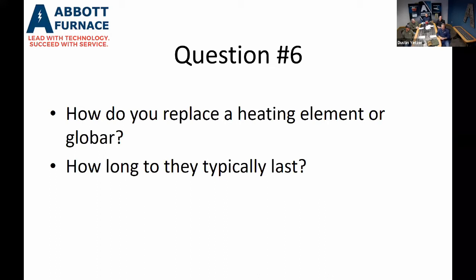But glow bars, if you break one glow bar and you replace just the one, and they're usually connected 2 in series, then you start seeing an imbalance in your amperage and voltage. Old glow bars typically have their resistance increase as they wear. So if you put a new glow bar in with an old glow bar, the new glow bar is actually going to work harder than the old glow bar, and you'll start wearing that new glow bar out faster.